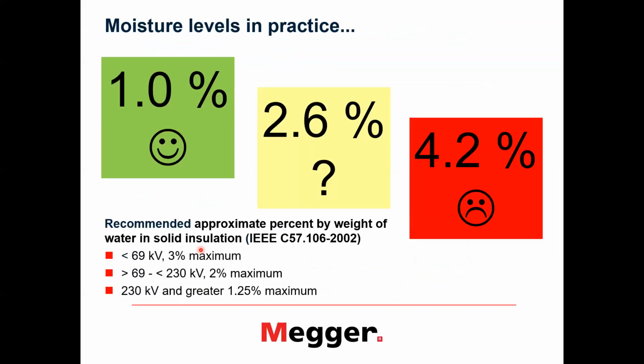So in practice, it is very difficult to say what moisture contents we should allow and which not. It also depends on what function the transformer performs in the network, whether it is a critical, huge transformer, or just a distribution transformer for some, I don't know, remote location where people don't live, and maybe just in the summertime.